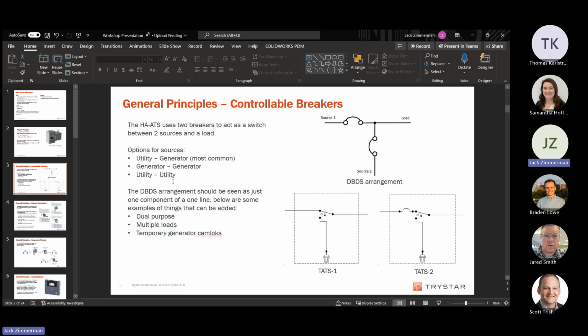There are some considerations later on with the different sources, and this needs to be in the quote we get from CX, because it's really important to know exactly what they're trying to do. This should also be covered in the riser diagram, which is also a required concept to get from CX - the context of these units and the availability of power really matters. It also supports utility connections, and these are generally the easiest because you don't have any auto start capability or controls related to the generators.